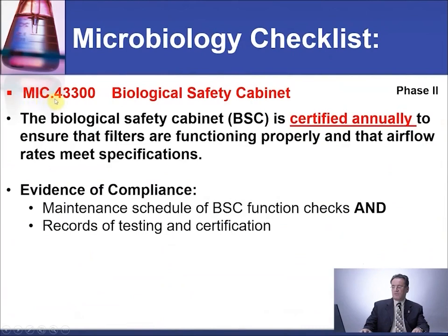In MIC.43300, biological safety cabinet, you need to have it certified annually, and you need a certificate. Usually the hospital or the laboratory hires a company from outside to come and do it, or it can be done by maintenance or biomed if they are trained to do it.